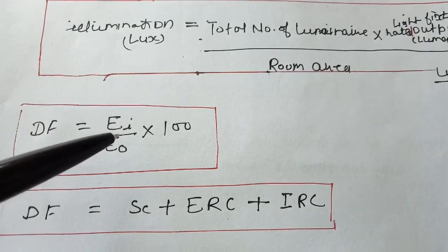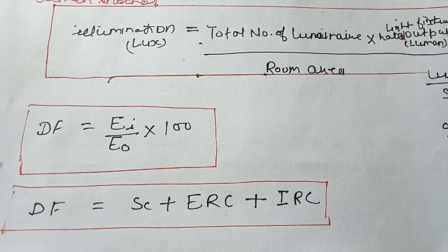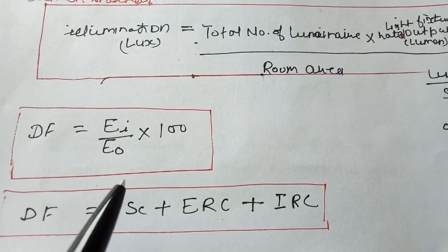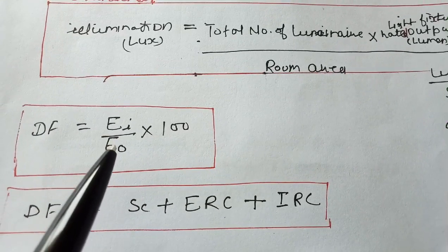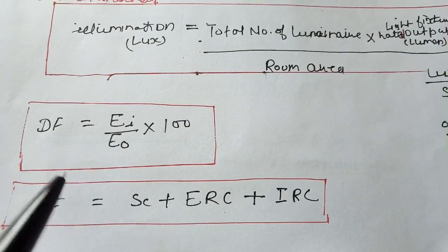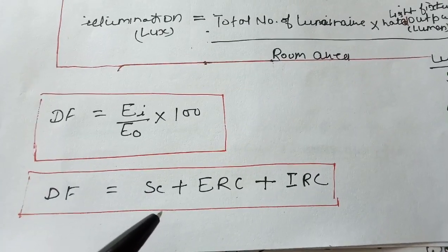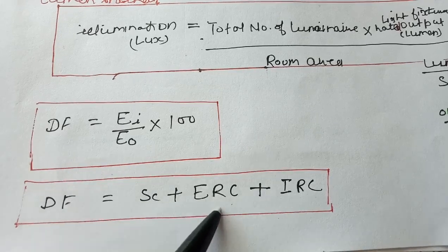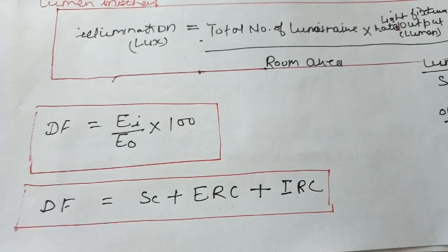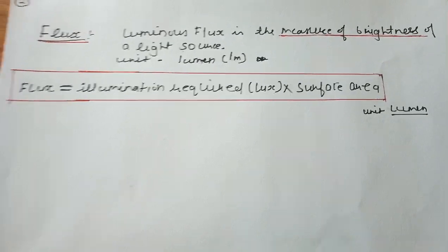We also use illuminance for calculating the daylight factor, which is illumination inside divided by illumination outside. The daylight factor is also equal to the sky component plus the external reflected component plus the internal reflected component. We will discuss daylight factor in more detail later.